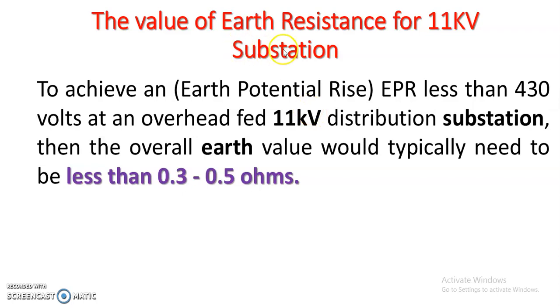So the value of the earth resistance for an 11 kV substation is the most important part. To achieve an earth potential rise, that is EPR, of less than 430 volt at an overhead fed 11 kV distribution substation, that means a pole mounted substation, the overall earth resistance value would typically need to be less than 0.3 to 0.5 ohm.